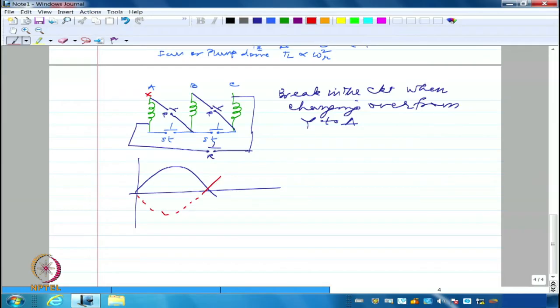So these are generally inherent problems faced in such applications where I'm going to break the circuit and reconnect the circuit. So this is breaking the circuit and reconnecting the circuit once again. This is one of the problems we normally may face in star delta starting. So one is EB, the other one will be V applied. So if they are completely out of phase, then I'm going to have a major issue. Right?